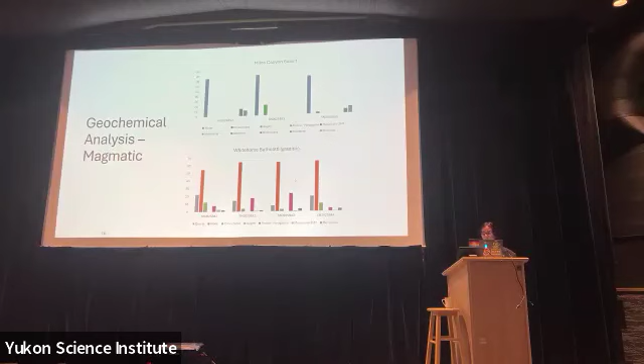And then within the porous formations, which would be the basaltic formations and the saturated sediments, we have a global mean of about 1.5 watts per meter Kelvin. And this is really important information that we can use in sizing potential ground source heat pump systems in the future. Another really important metric for ground source heat pump systems is the temperature of the ground.